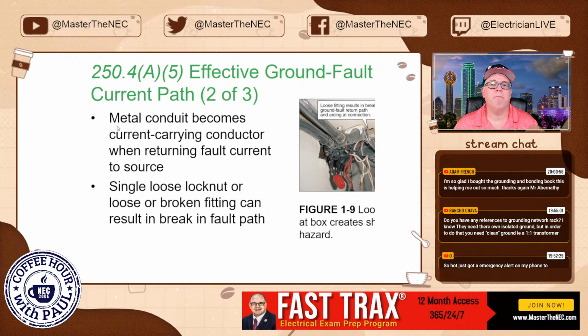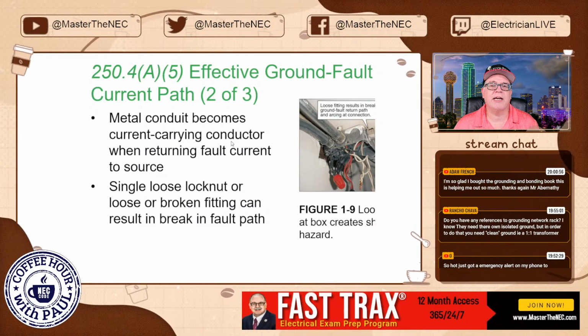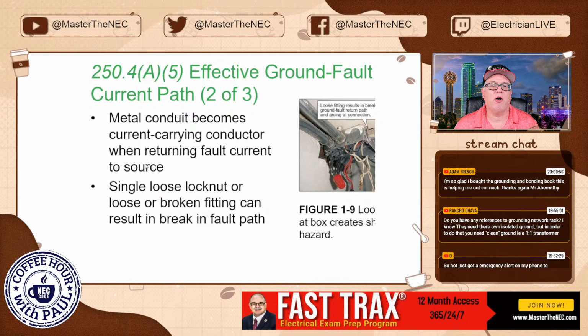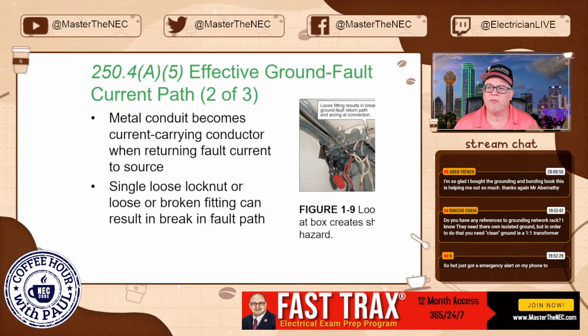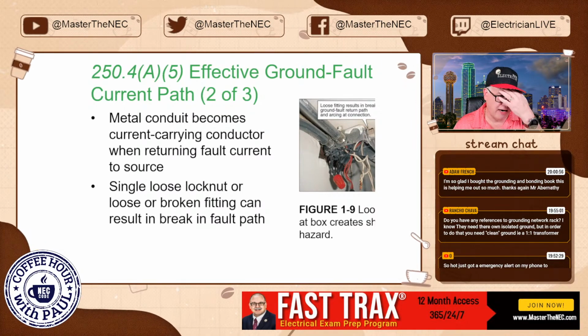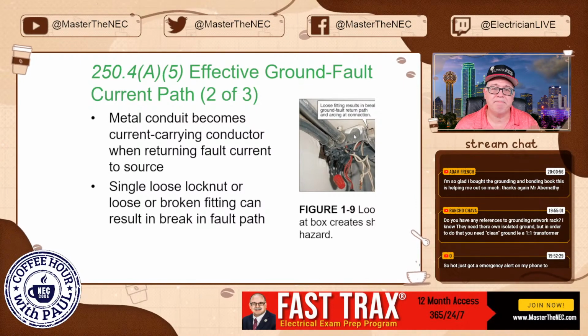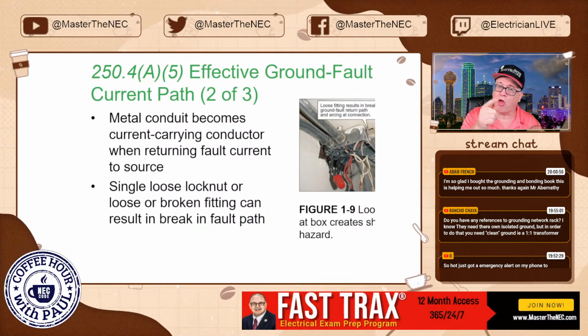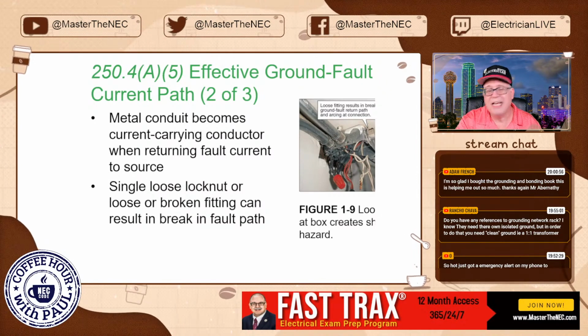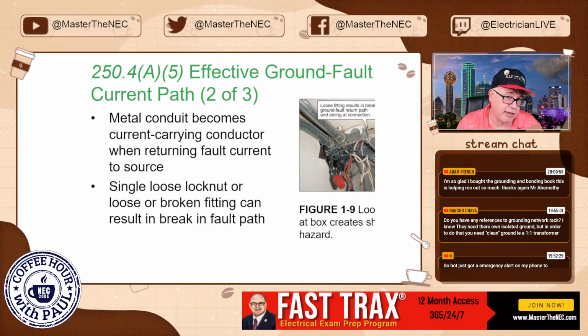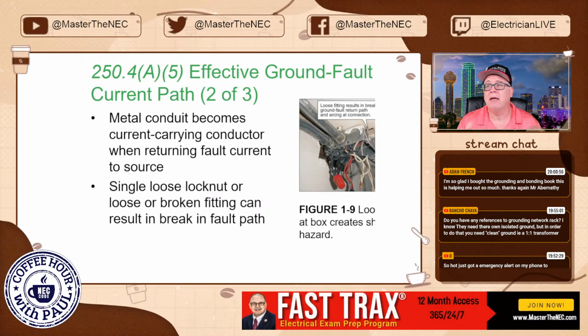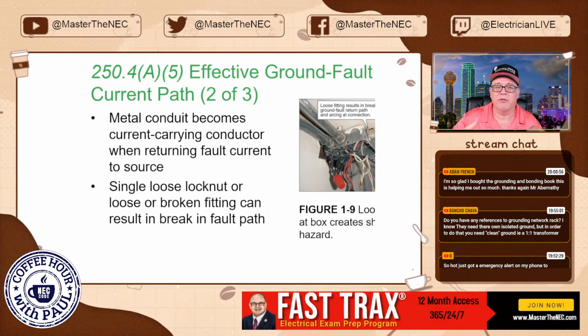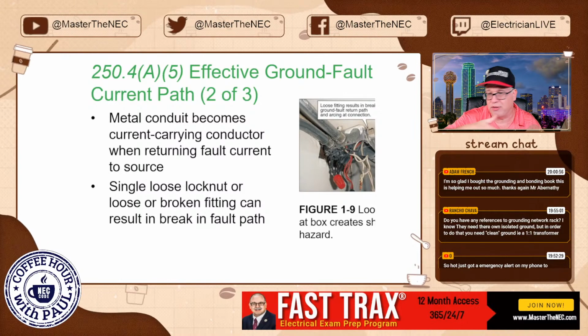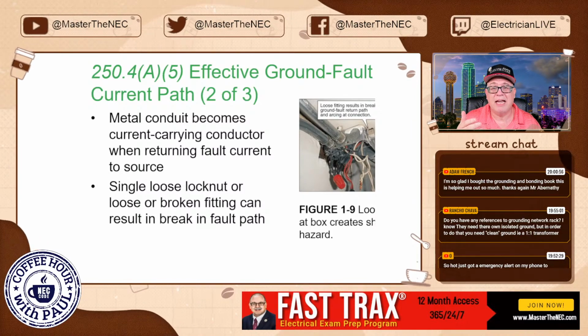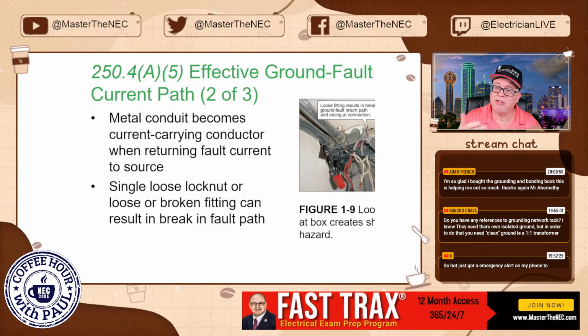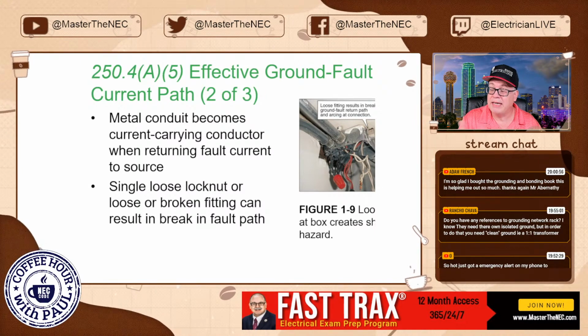Next, effective ground fault, metal conduit becomes current carrying conductor when returning fault current to the source. Absolutely it does. So if I have this EMT, as you see right here, and there's a fault onto it, it is going to be a current carrying conductor. Although, don't let that confuse you. It is not to be counted as a current carrying conductor when we're doing things like the number of current carrying conductors and adjustments and corrections and all that kind of stuff. But in a fault condition, ground fault condition, it will obviously carry current.